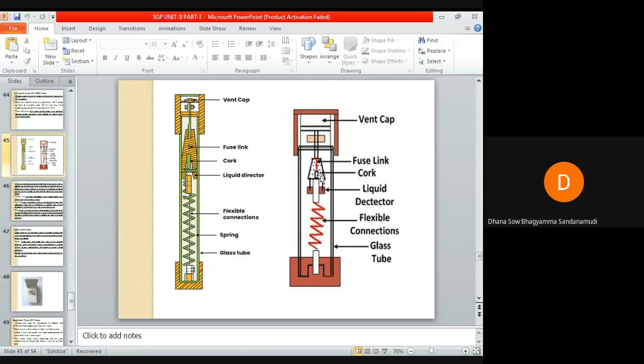So when current exceeds the required or prescribed limit, which means whenever a fault occurs and the current becomes excessive, this fusing wire will melt. As soon as the fuse melts, an arc is struck between these two terminals. So even though the fuse has melted, there is continuity of discharge of electrons in between these two terminals. And the spring will retract part of it through a baffle, that is the liquid detector.